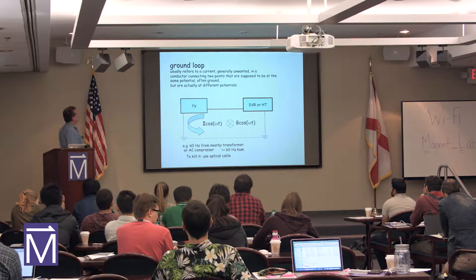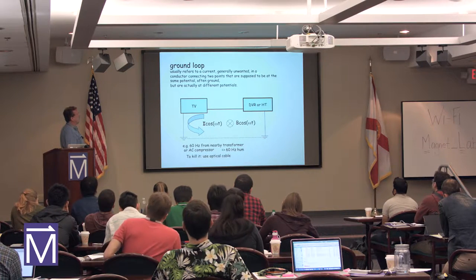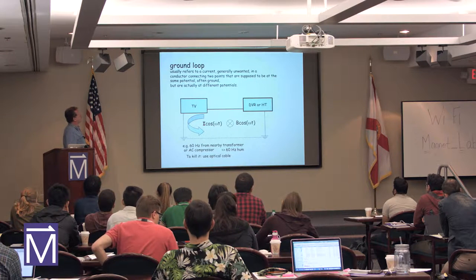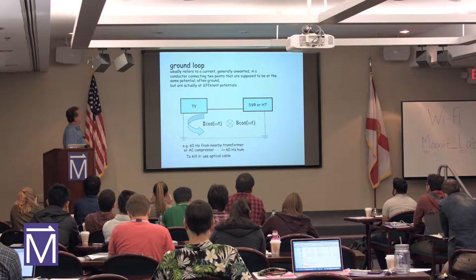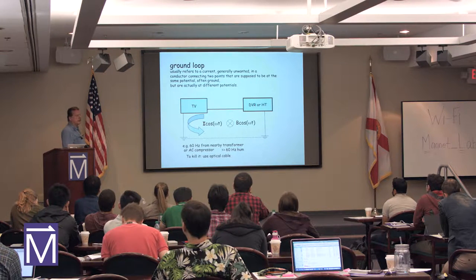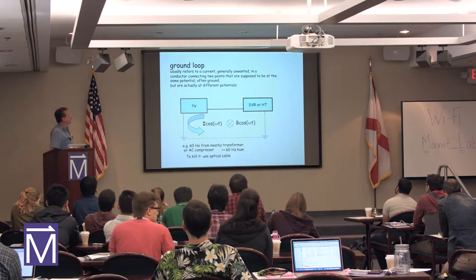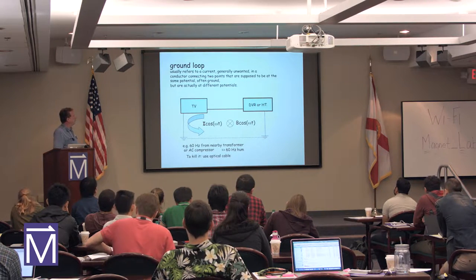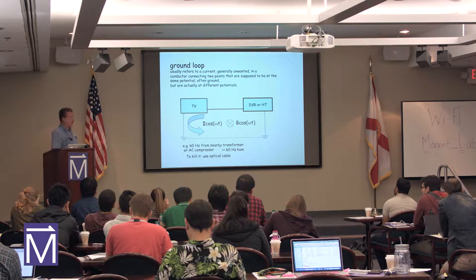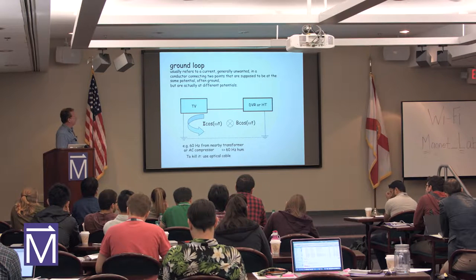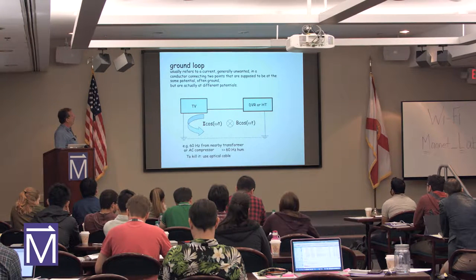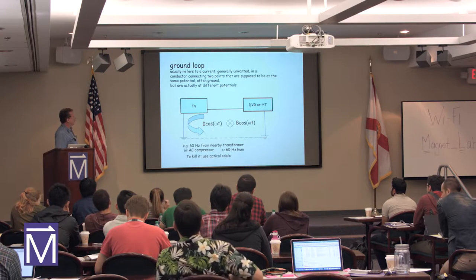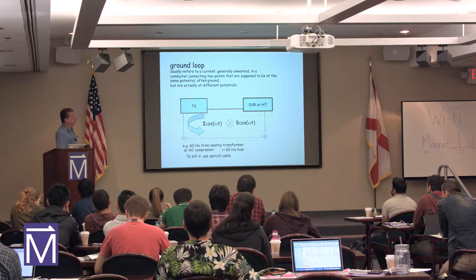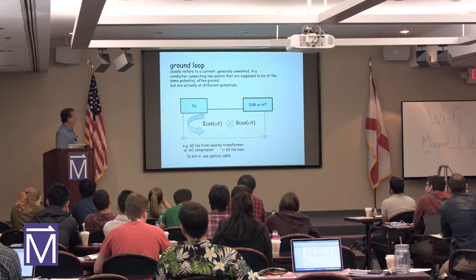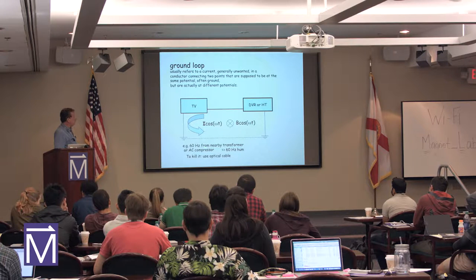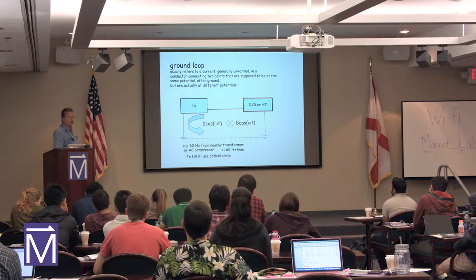So what is a ground loop? It usually refers to a current, generally unwanted, in a conductor connecting two points that are supposed to be at the same potential, often ground, but are actually at different potentials. This is an example, TV set and DVR or home theater, which are connected because of the acoustic signal from the TV, and they are both grounded. In this loop, some alternating field is always present from transformers and so on, usually 60 hertz, and it results in 60 hertz hum in acoustic signals.